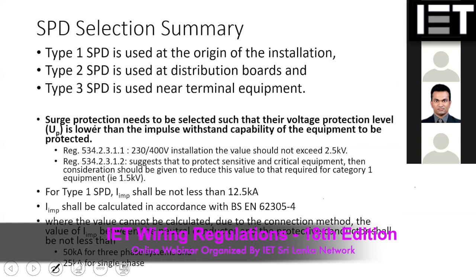And this is the summary, because as I said, there will be a few pages of the regulations. When you look at the summary of the SPD selection, what they are telling is you have to have the type 1 for the origin of the installation, the type 2 at the distribution board, and the type 3 at the terminal level. If you use this type of cascaded arrangement, you can minimize a lot of the transient over voltage damages.